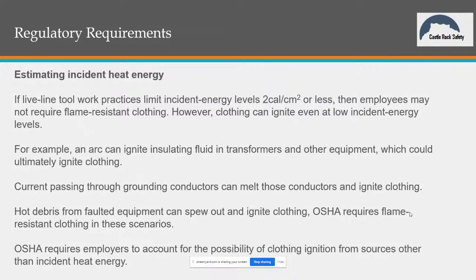One thing here, remember we talked about the 2-calorie boundary. What OSHA expects us to do on the utility side is determine where that 2-calorie boundary is. And if you are going to be within that 2-calorie boundary, then you have to wear clothing that is equal to or greater than whatever that incident energy is inside that boundary. Now, what they also tell us, and we'll talk about this later, is if you're out there on a distribution line and you've got a 2-calorie boundary calculated at 15 inches.